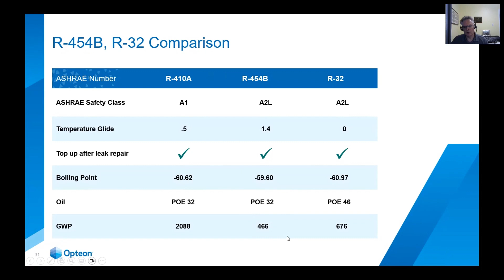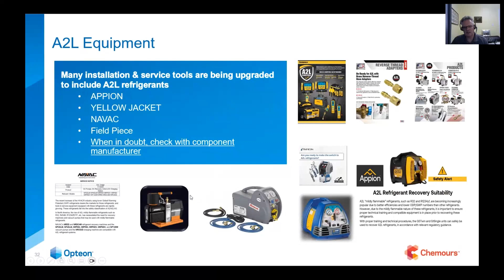So let's talk quickly about equipment. The service equipment, what's different? Really the difference is going to be the valve fitting. There are adapters available. Certainly if you're using a gauge set on different refrigerants, don't cross-contaminate. But when we look at the recovery machines and the vacuum pumps, they've been available for a few years now, so you may already have a unit that's compatible or approved for the A2Ls. But if you're buying a new one in the next year or two, make sure you're looking at one that's got the sticker on the box that says it's approved for use with A2L refrigerants.